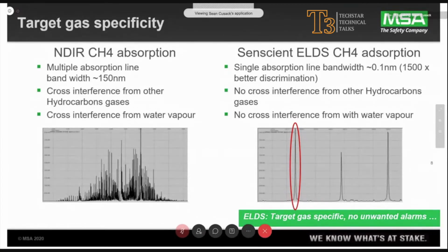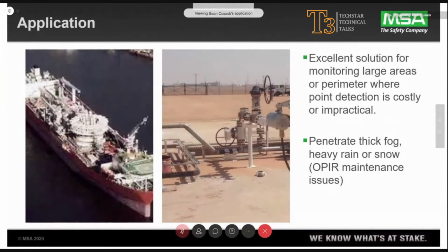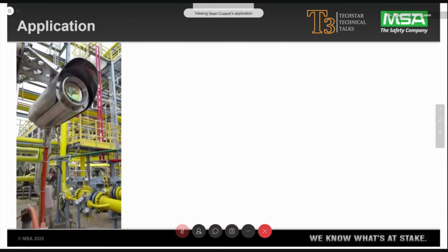Is there really zero maintenance? As far as I know, unless it gets hit by a person or a truck, you would have to realign it. There's no calibration, there's no testing, etc. I mean, you can do a sensor gas test on it anytime you want. Otherwise, it's happening every 24 hours.